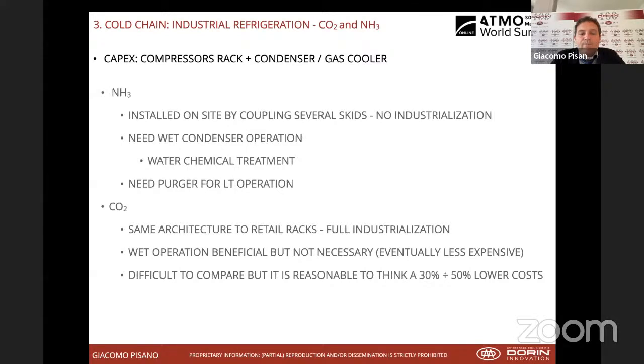When we talk about CO2, the architecture of a booster rack is basically the same as the ones being used in the supermarket business. So there is a very strong industrialization available for racks, which brings down the cost. Let's say that adiabatic cooling is beneficial, but is not necessary. So either you save money or you bring in some more efficiency. Clearly, from a capital expenditure, it is difficult to compare, but for a branched system, so not for a chiller, but for a branched system, a lower cost between 30% to 50% is doable when talking about CO2 against ammonia.